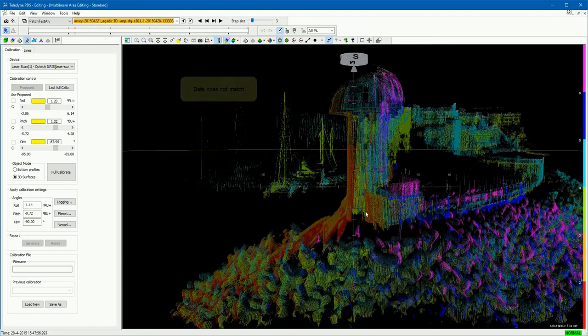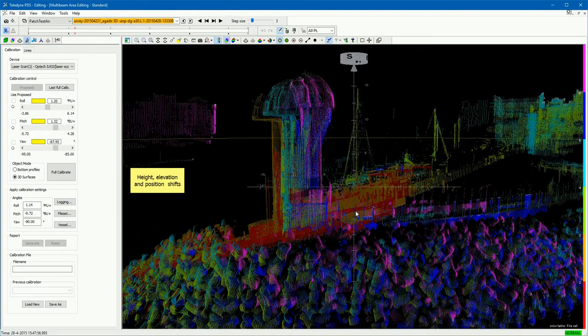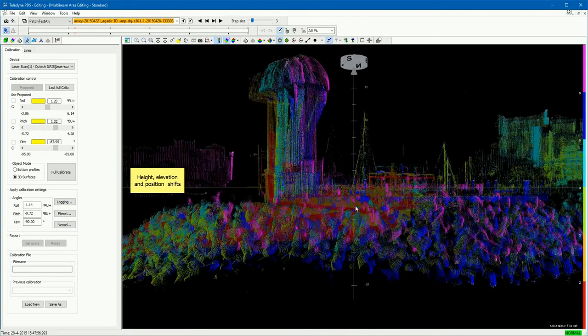The customer complains the data of different survey lines does not match. Artifacts such as height and elevation shifts are noticed. Use the PDS calibration utility to calibrate the LIDAR laser mounting angle offsets.